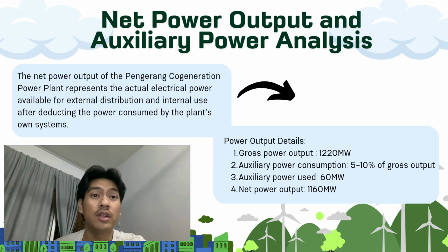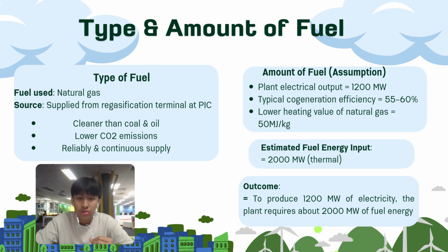The first one is the gross power output, which is 1220 megawatt, and for the auxiliary power consumption we get 5 to 10% of gross output. So the auxiliary power use is 60 megawatt, and the last calculation we get the net power output is 1160 megawatt. So I'm going to be presenting about the type and amount of fuel.